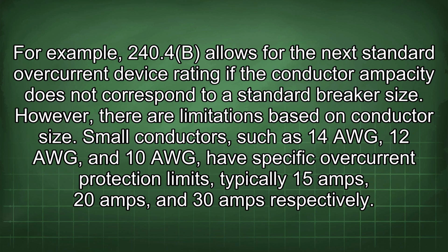240.4(B) allows for the next standard overcurrent device rating if the conductor ampacity does not correspond to a standard breaker size. However, there are limitations based on conductor size. Small conductors, such as 14 AWG, 12 AWG, and 10 AWG, have specific overcurrent protection limits, typically 15 amps, 20 amps, and 30 amps respectively.